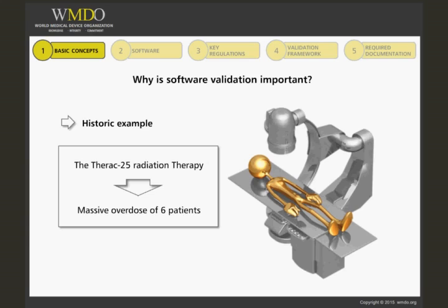A first incident had been reported to the manufacturer two years earlier, but the malfunction occurred rarely and was difficult to reproduce, so it took a long time before the existence of a software glitch was recognized by the manufacturer. The tragedy highlighted the dangers of software control of critical systems and led to the FDA strengthening policies on incident reporting, as well as stricter regulations on the use of software in medical devices. In spite of these efforts, malfunctions caused by software deficiencies remain frequent in medical devices and keep leading to accidents.